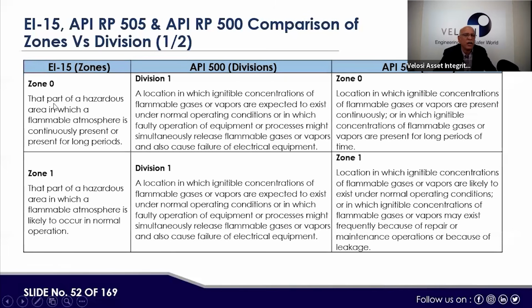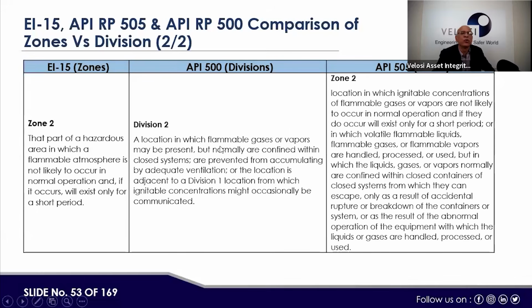Zone 0 we already defined earlier. This is the part of the hazardous area in which a flammable atmosphere is continuously present or present for a longer period. From a definition point of view, zone 0 is a location in which ignitable concentrations of flammable gases or vapor are present continuously, or for longer periods. Here we call it division 1. Practically, in API 500, zone 0 and zone 1 are combined under division 1. This is the difference, whereas in EI 15 and API 505 there are zone 0 and zone 1 separately. Then zone 2 is called division 2 in API 500 and zone 2 in the others. This definition I already covered earlier.